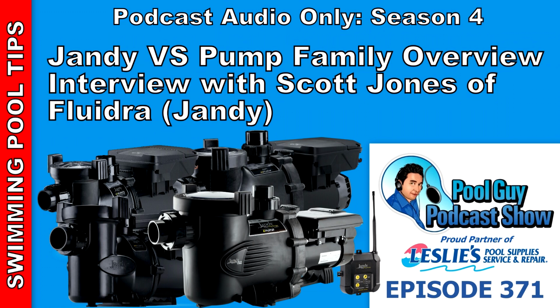What's nice there is 1750 RPM is a great speed for, say, a saltwater chlorinator. So when your pump is above 1750 and you have a saltwater chlorination system, that system will turn on and will generate chlorine. As long as that pump is over 1750 RPM, it's still, from a variable speed pump standpoint, a great energy saving speed. It's half speed. You're saving almost 90% on your energy bill by operating at that speed.